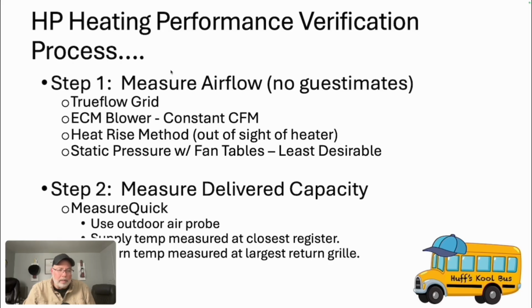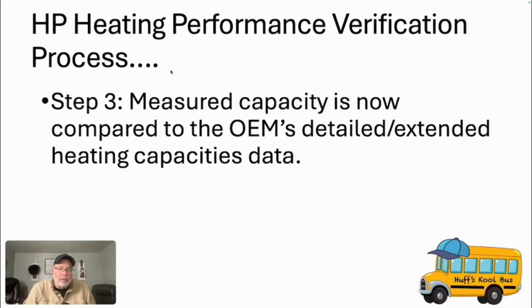Right, step 1, measure the airflow, no guesstimates. Step 2, measure the delivered capacity. Now, if you're using MeasureQuick, when you're going through your indoor information in your gauge view and you go to indoor, you can actually enter the measured airflow. That way it's going to use that number that you measured in calculating the delivered capacity. So you want to make sure that you do that.